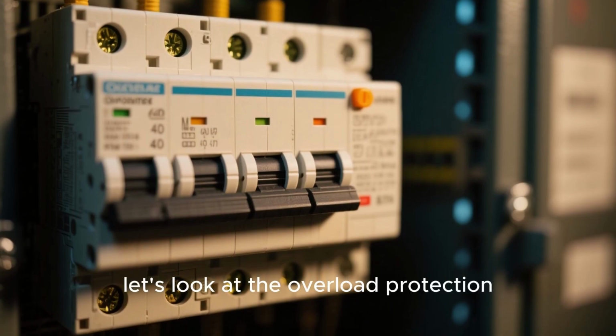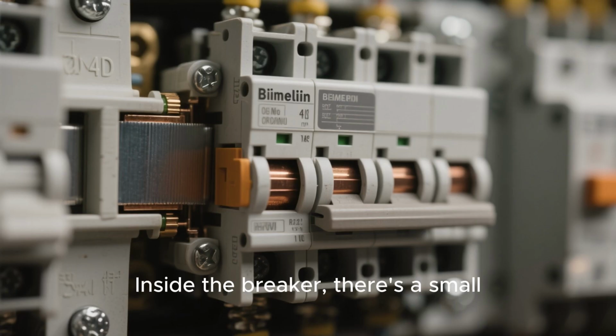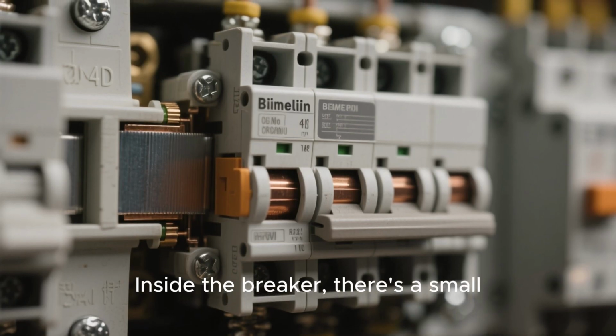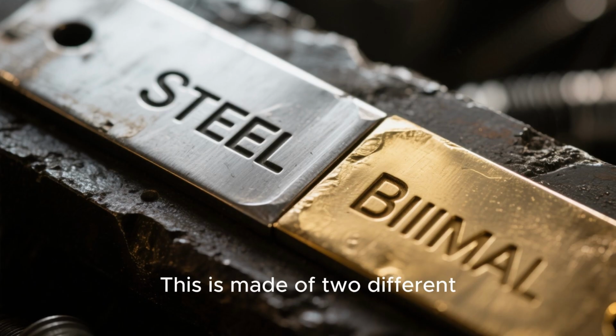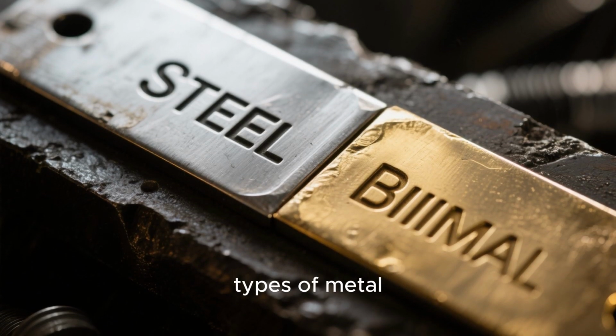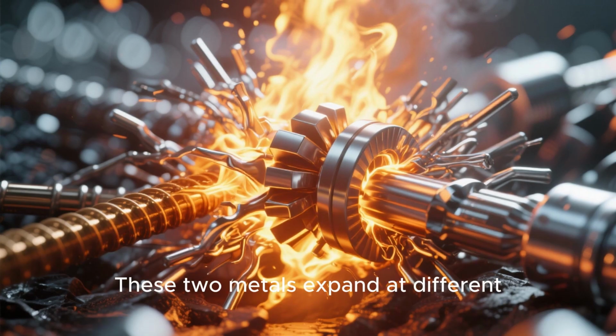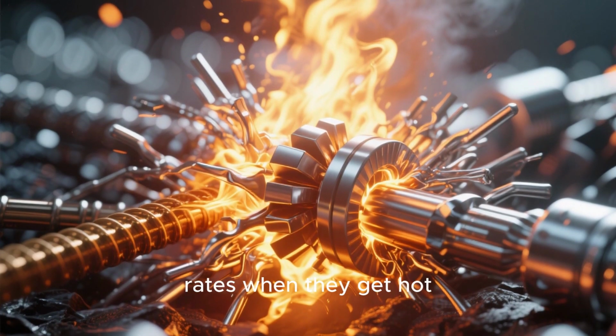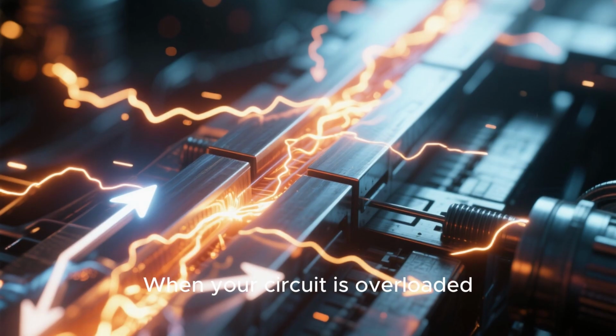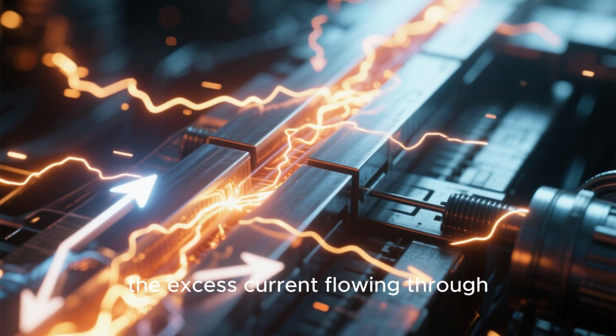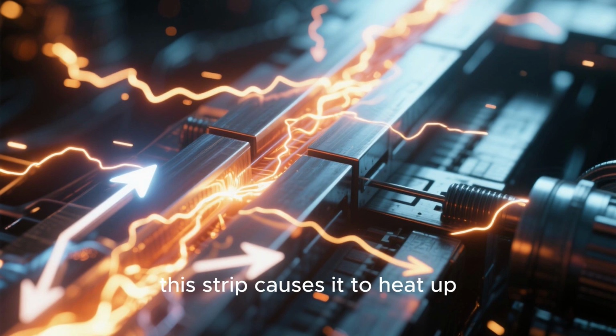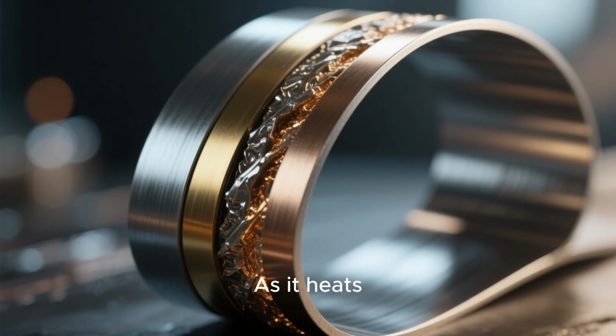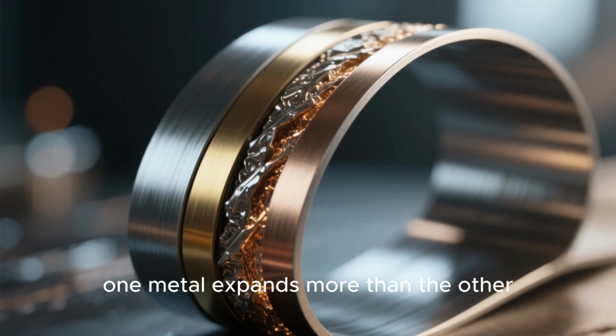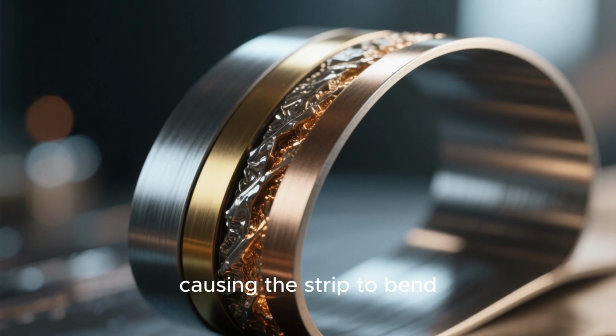First, let's look at the overload protection. Inside the breaker, there's a small, clever component called a bimetallic strip. This is made of two different types of metal, like steel and brass, bonded together. These two metals expand at different rates when they get hot. When your circuit is overloaded, the excess current flowing through this strip causes it to heat up. As it heats, one metal expands more than the other, causing the strip to bend.